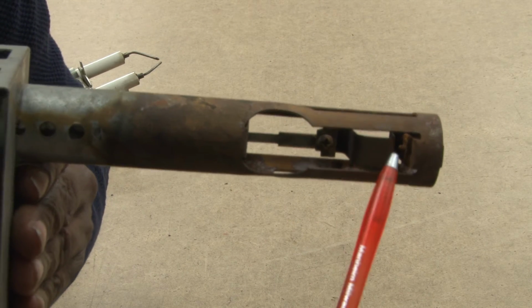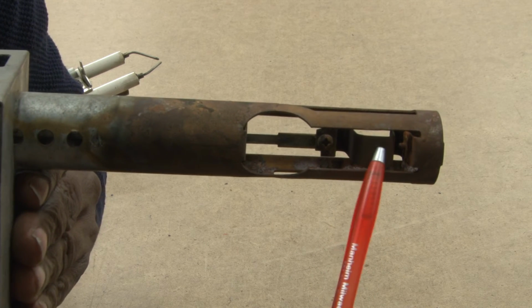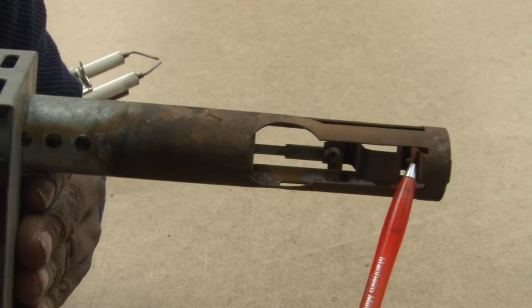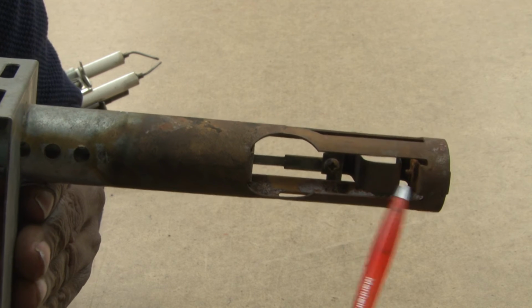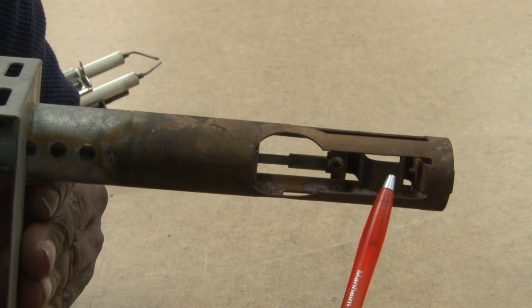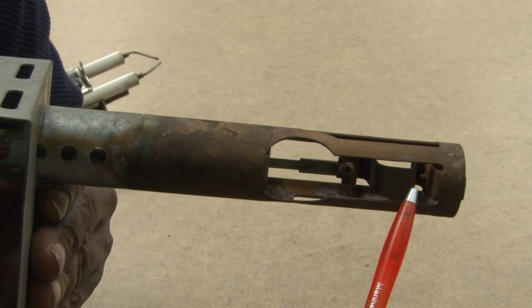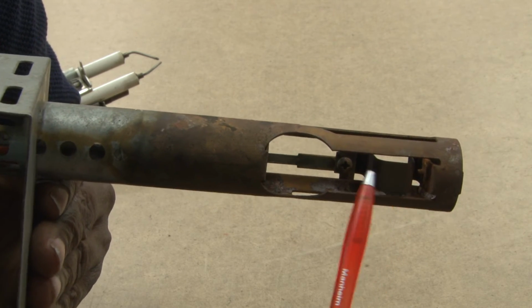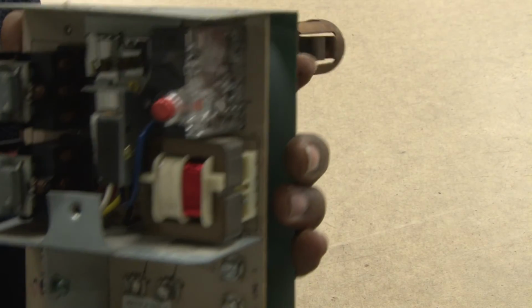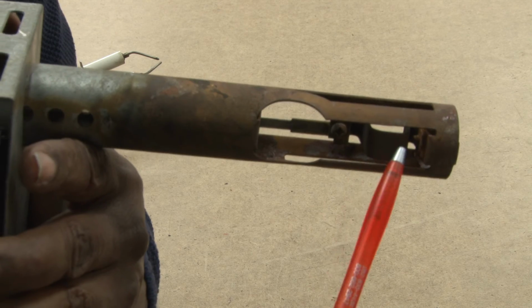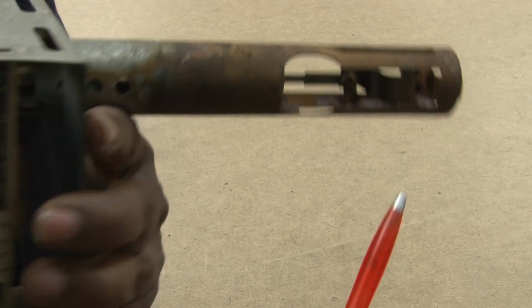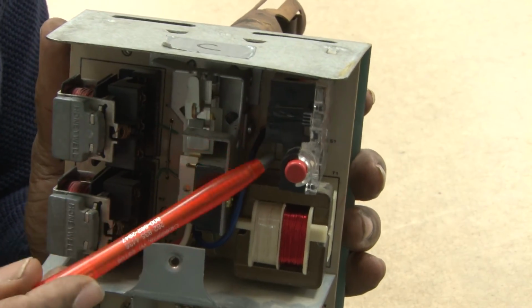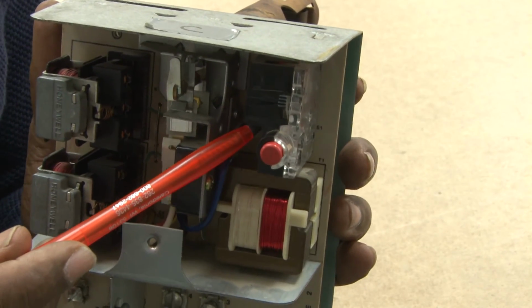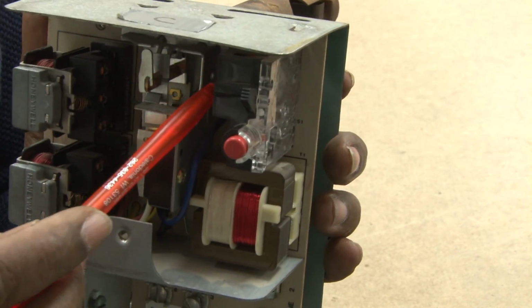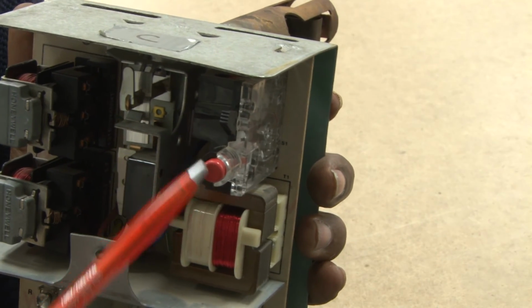So it was a bimetal coil that was inside of the stack. Once it received heat from the burners operating, and it took quite some time for it to happen, in minutes, the bimetal will deflect and cause a mechanical action to keep it operating. But if it didn't have the heat to activate the bimetal, there's basically a heater inside of it, the heater switch.